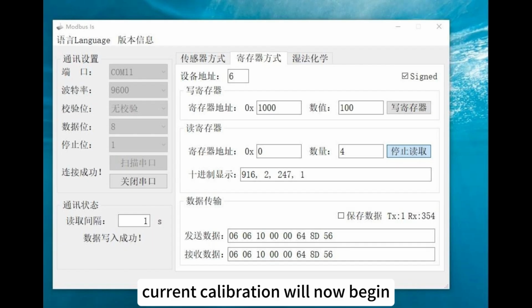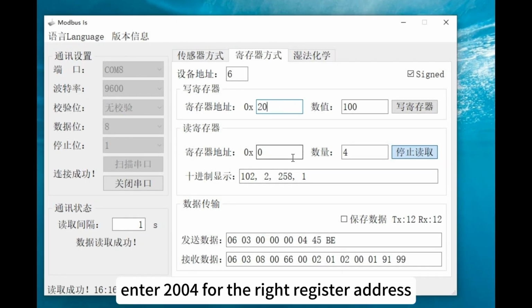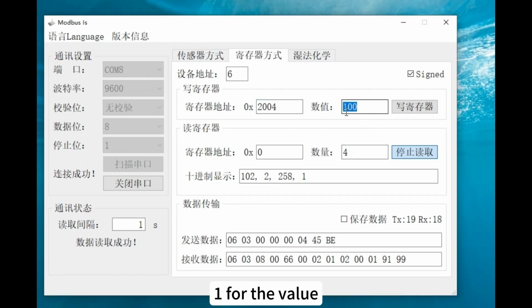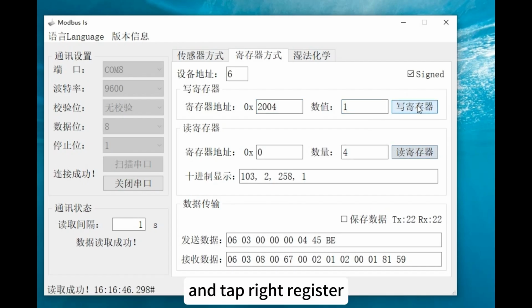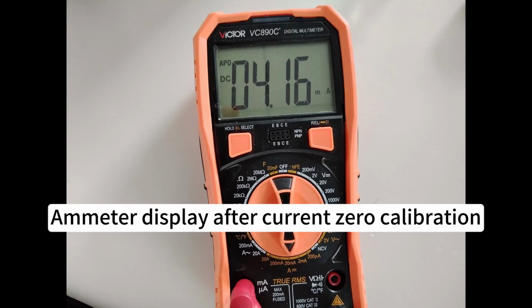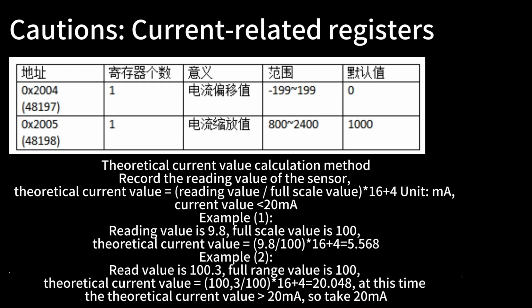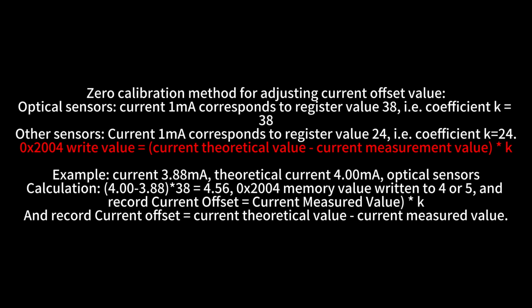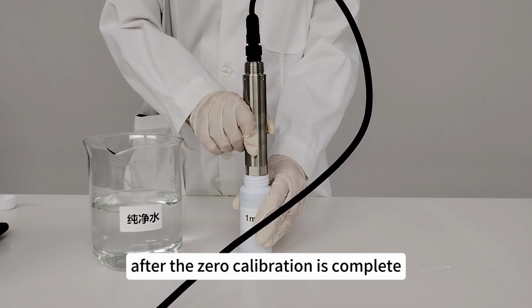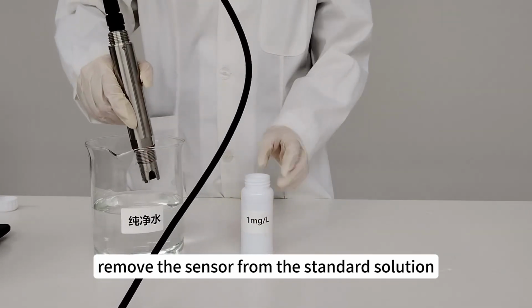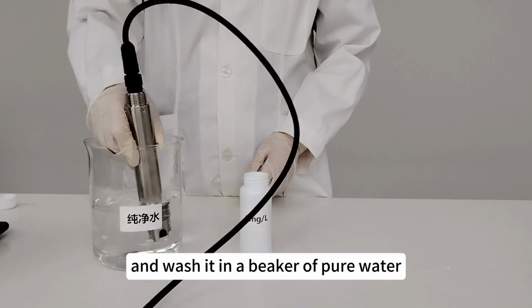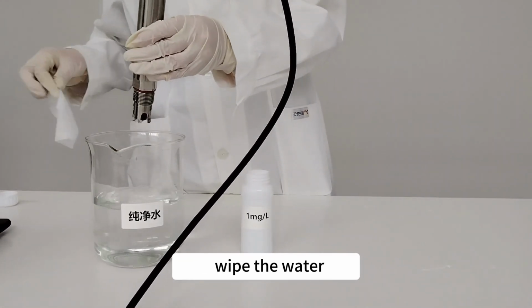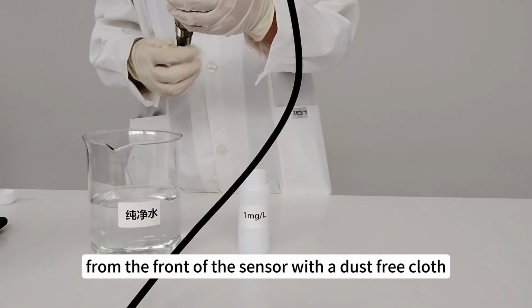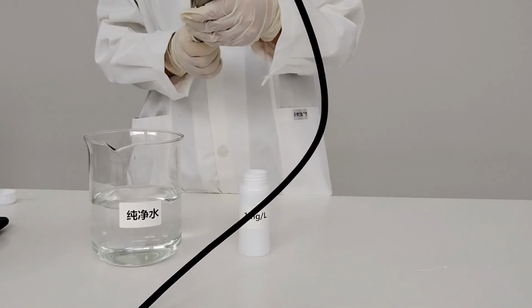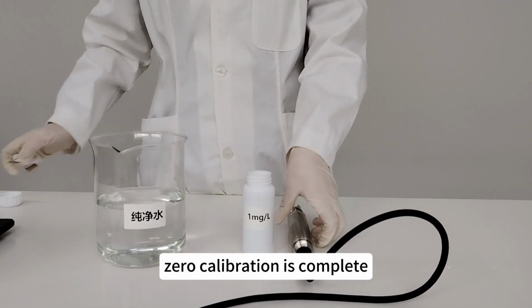Current calibration will now begin. Enter 2004 for the write register address, 1 for the value, and tap write register. Tap read register again. After the zero calibration is complete, remove the sensor from the standard solution and wash it in a beaker of pure water. After cleaning, wipe the water from the front of the sensor with a dust-free cloth. Zero calibration is complete.